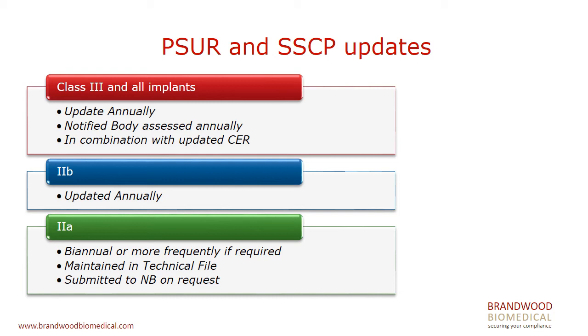So if you've got a high-risk class 3 device or an implantable medical device, you have 3 reports which will now be required to be reviewed every year by the notified body. That's 3 extra reviews, and for which, of course, you'll be paying review fees.